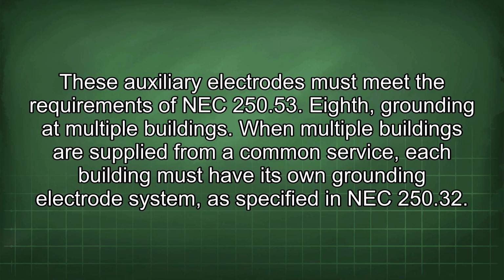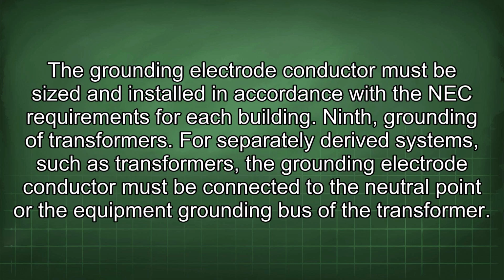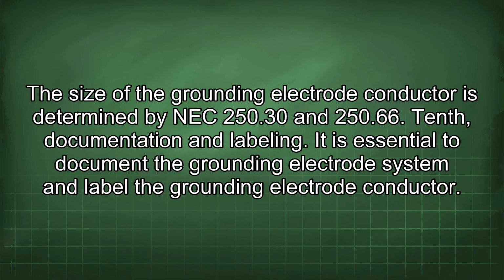Eighth, grounding at multiple buildings. When multiple buildings are supplied from a common service, each building must have its own grounding electrode system, as specified in NEC 250.32. The grounding electrode conductor must be sized and installed in accordance with the NEC requirements for each building. Ninth, grounding of transformers. For separately derived systems, such as transformers, the grounding electrode conductor must be connected to the neutral point or the equipment grounding bus of the transformer. The size of the grounding electrode conductor is determined by NEC 250.30 and 250.66.